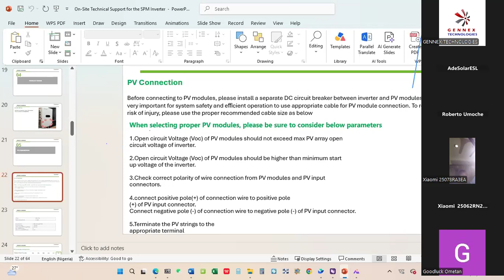Yeah, like we said, this is the cable size you have to use on the PV side. Then we have, if you can see the inverter model, the PV input. We talked about this. This is a specification of the panel data sheet. So when connecting your inverter, always take into consideration the specification of this data sheet. Like the short circuit current of this panel is 14.96, and we already said that the 8000 TL can take 16 amps. So when you are connecting two strings of panels in parallel, you are already increasing the current, and you have exceeded the current rating of the MPPT of the inverter. So always put that into consideration.